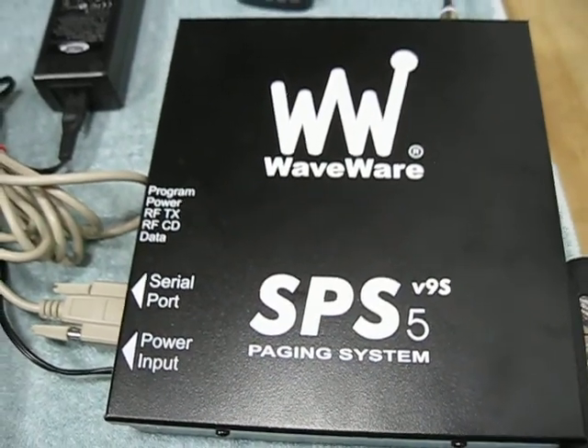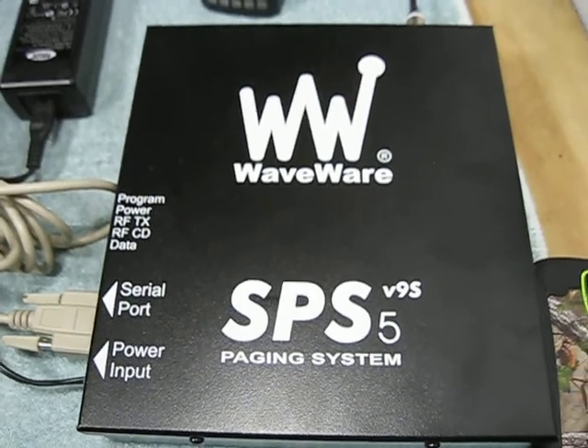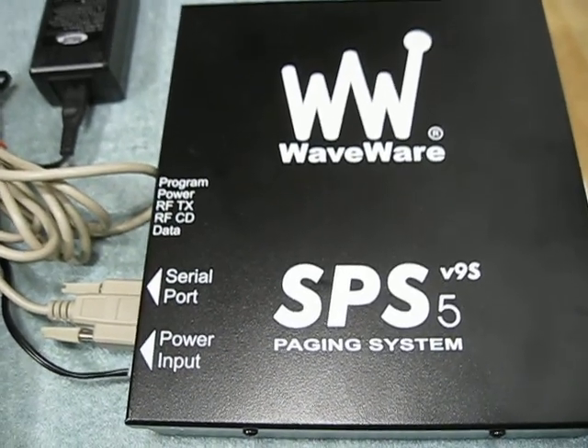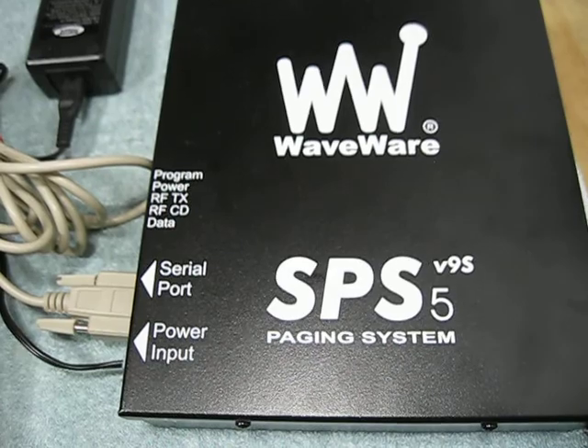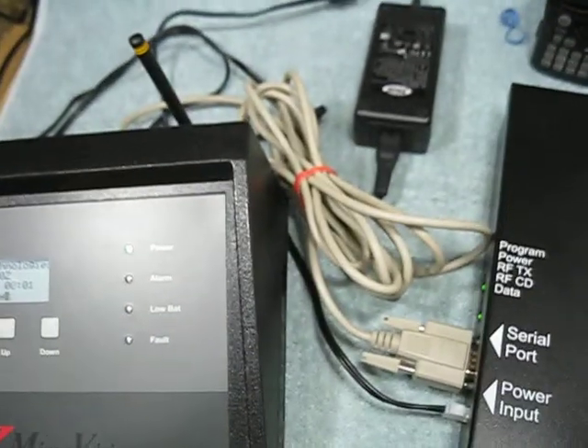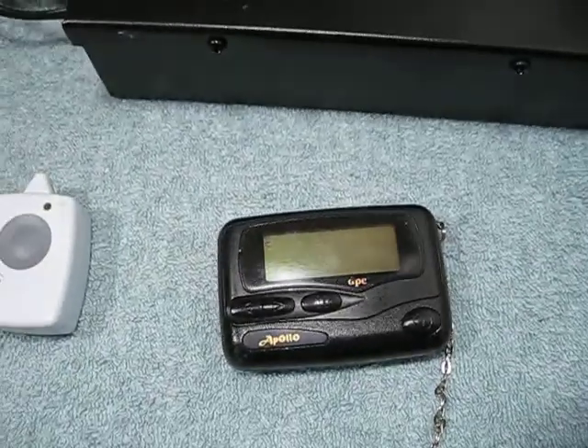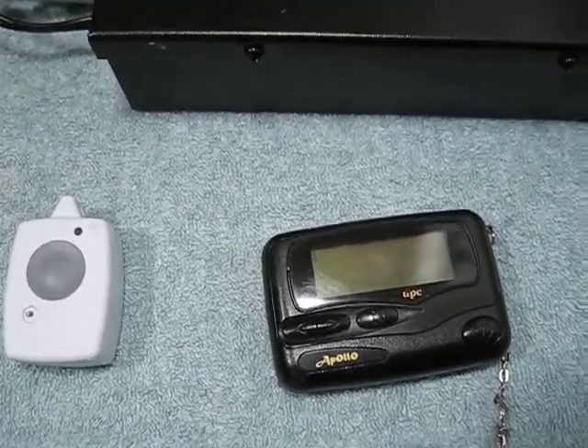This is a POCSAG WaveWare SPS5 v9S unit. It's a UHF transmitter, transmits at 512 baud, and is currently configured for a narrowband signal in the UHF spectrum. Once it receives data through that cable, it transmits that data out through the rubber duck antenna, where it's received by any paging unit on site at the rehab facility.